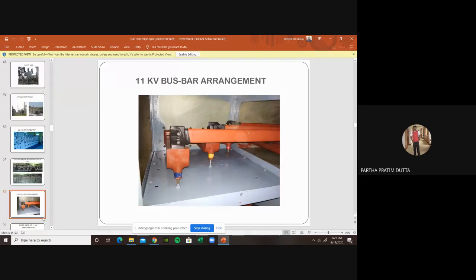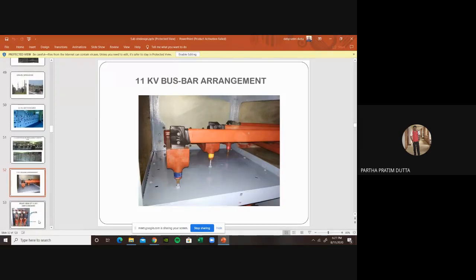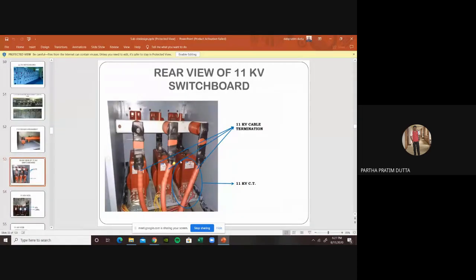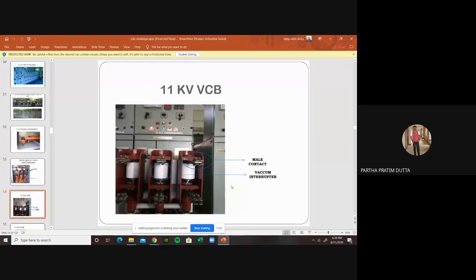Okay, now this is the CT, at the back side of the 11 kV switchboard where the CT is placed, and this is the secondary terminal of the CT. The current is usually emanated through this secondary terminal to the relay system, and through the relay system it goes to the trip coil. That is the 11 kV CT, and this is the 11 kV VCB, the vacuum circuit breaker. The vacuum interrupter acts as the quenching medium, where arcing and heat are generated during making and breaking.